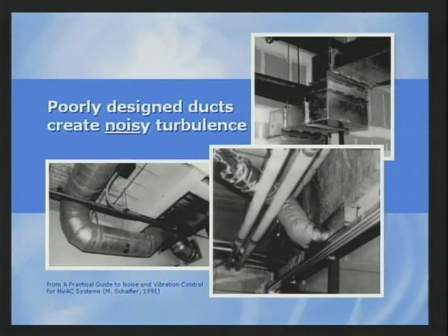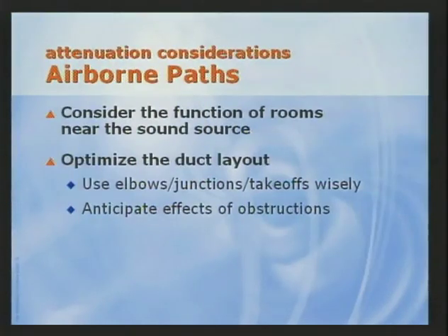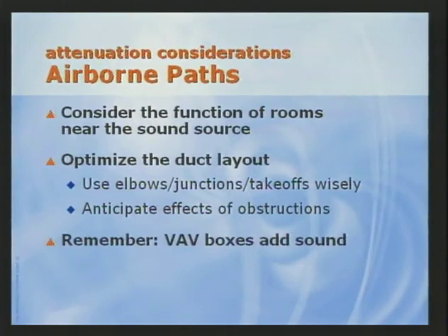These examples of poor duct installation practices come from the ASHRAE book titled A Practical Guide to Noise and Vibration Control for HVAC Systems, which is an excellent reference source for good design practices. In addition to ductwork, also review the terminal devices like VAV boxes when they are used. Even VAV boxes without fans generate sound, and this sound is added to the sound traveling down the duct. Some additional duct liner downstream of the VAV boxes may be necessary to absorb box-generated sound. VAV boxes also have a radiated sound component, so location of these devices is important. Acoustical considerations for VAV units are similar to those given for near-room units.